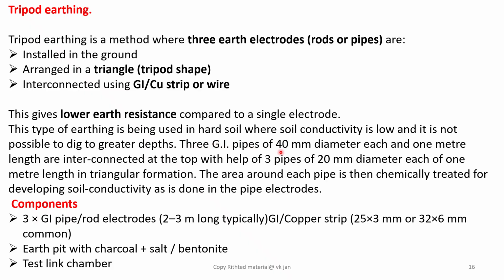Three GI pipes of 40 mm or more each and 1 meter length or even deeper are interconnected at the top with the help of three pipes of 20 mm diameter each of 1 meter length in triangular formation. The area around each pipe is then chemically treated for developing soil conductivity as is done in the pipe electrodes. The components of this system are three GI pipe rod electrodes, 2 to 3 meter long typically, GI or copper strip of size 25 by 3 mm or 32 by 6 mm common, and an earth pit with charcoal plus salt or bentonite. A test link chamber has to be provided.